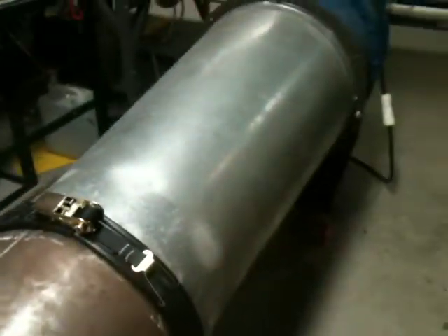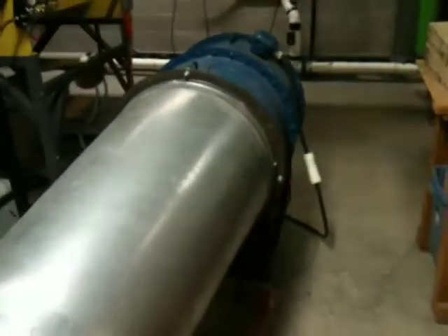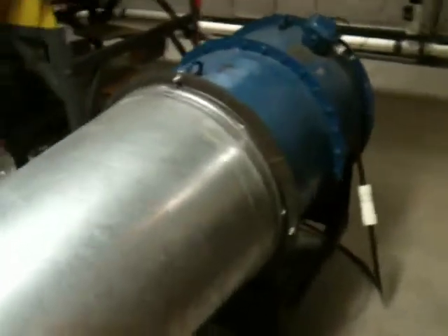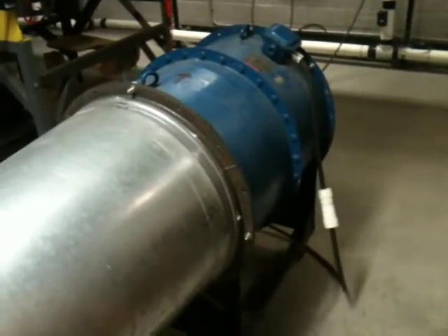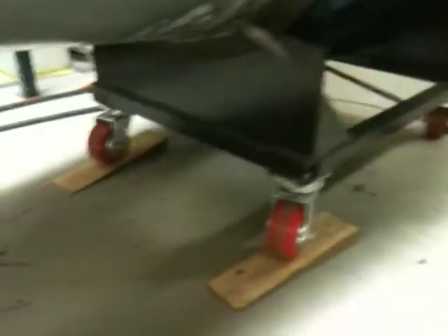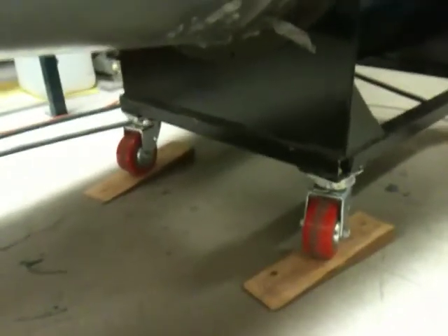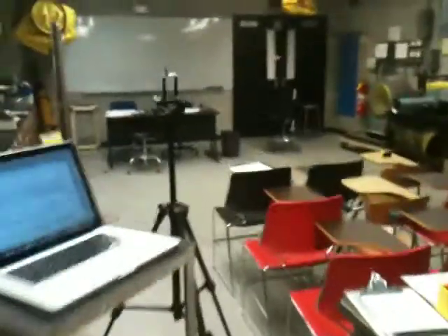And then here you can see that we've removed the 10 horsepower fan and we've replaced it with a single 5 horsepower fan. It's got a larger rotor diameter, so we have a conical transition adapter here. This fan doesn't fit in place quite as well as the 10 horsepower fan, so we have to prop it up on some wedges, but that's part and parcel of mining engineering, and it works very effectively. So bear with me while I put the camera back onto the tripod.